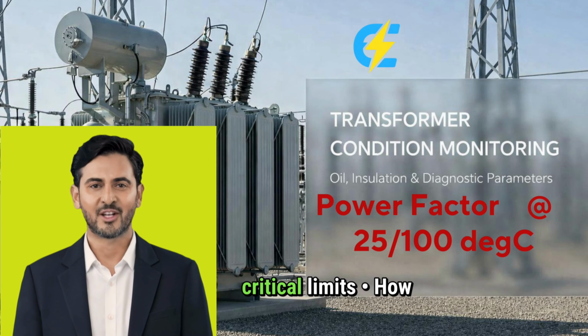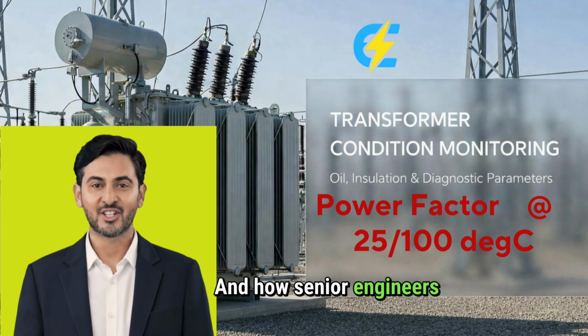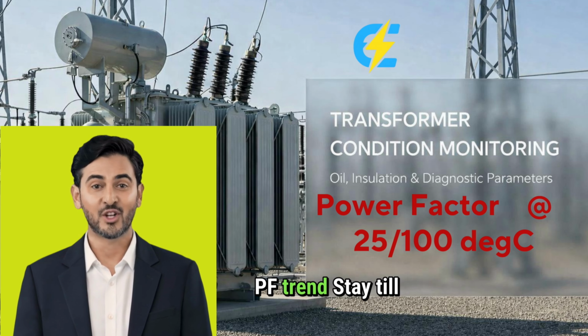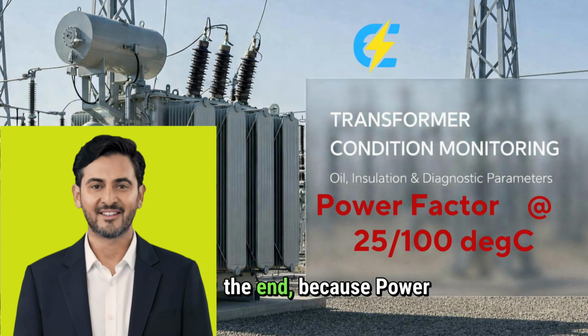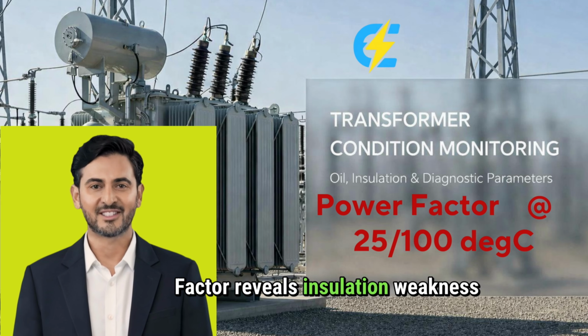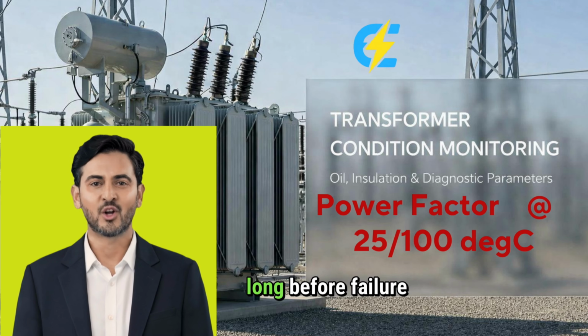Acceptable, caution, and critical limits. How PF correlates with TAN, IFT, and moisture. And how senior engineers judge insulation health using PF trend. Stay till the end, because power factor reveals insulation weakness long before failure.